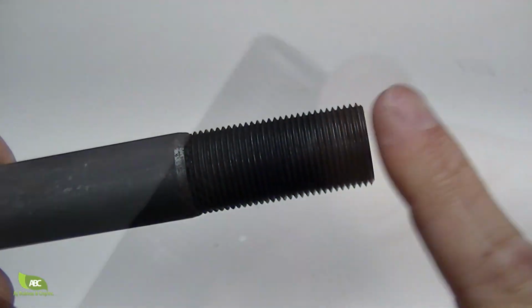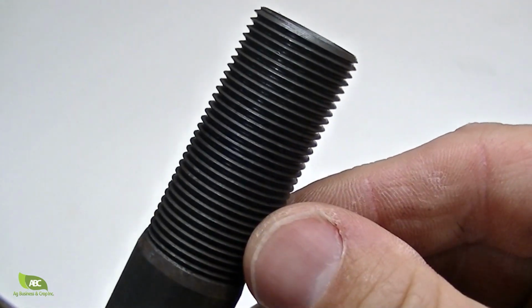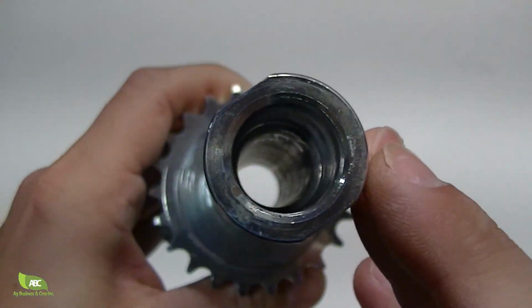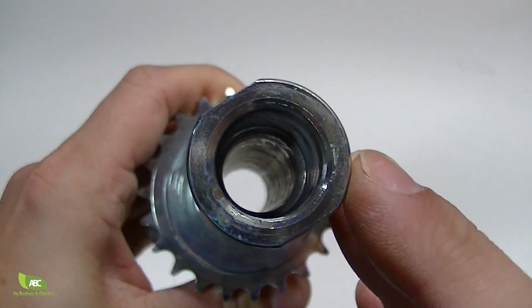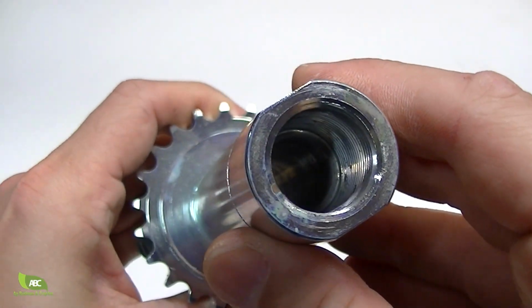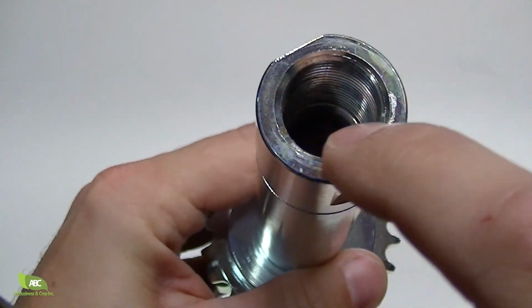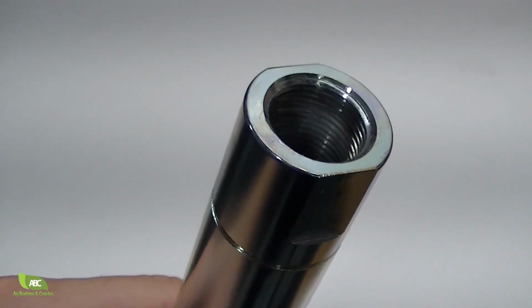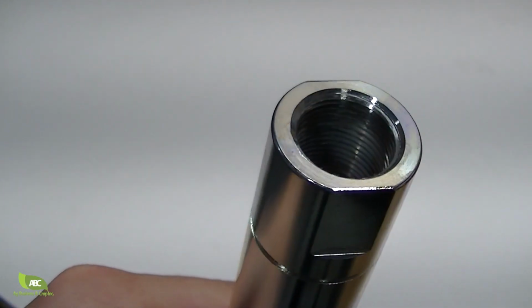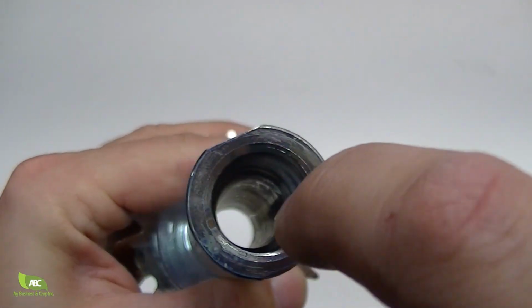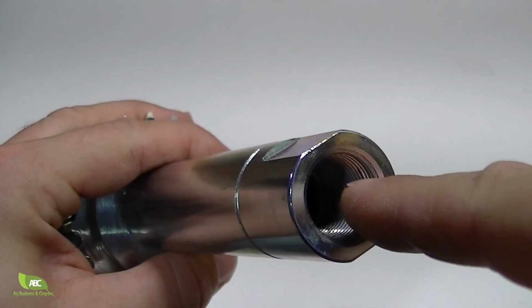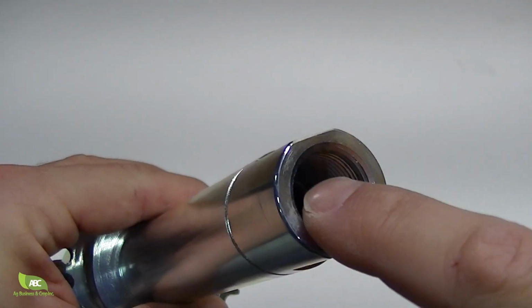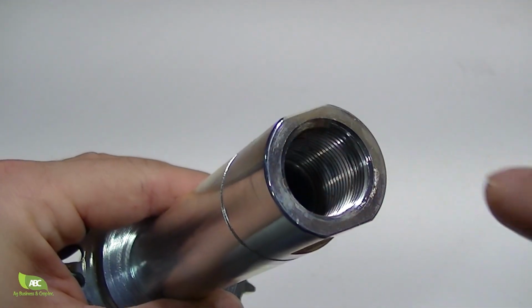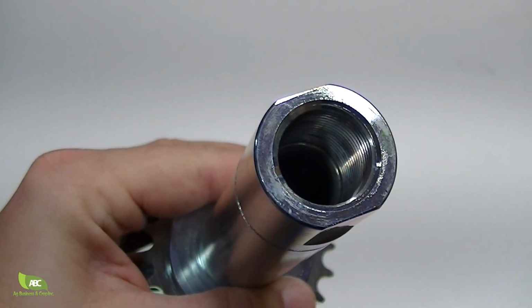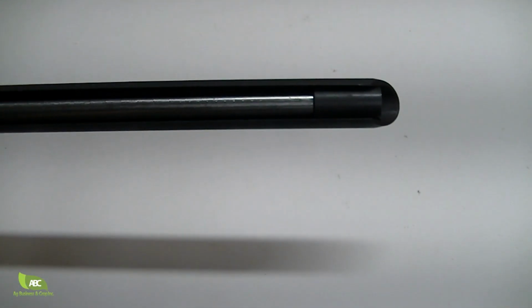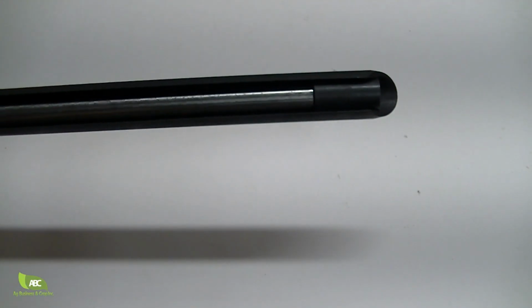Always check the threads on your new probe to see if it's clean. And most important, always check the threads on your probe hub. This is a more complicated part to be replaced, so you want to be sure the threads are clean and there's no damage on it. If you find any debris, you can always brush with a wire brush inside, and you can always re-tap and make new threads.